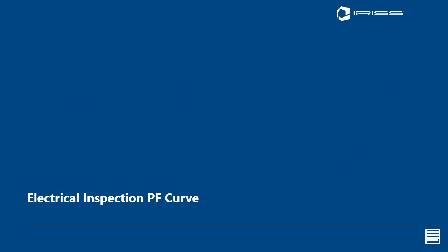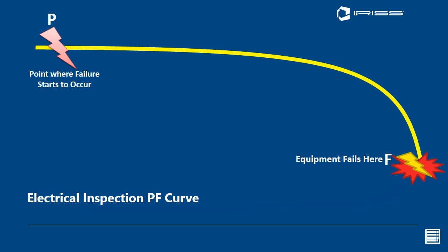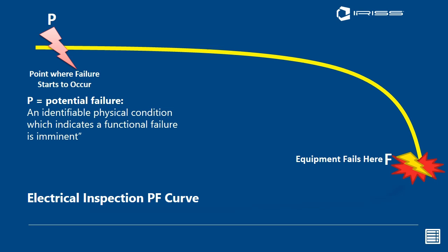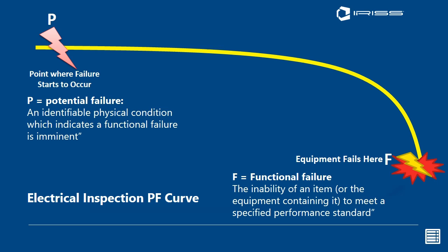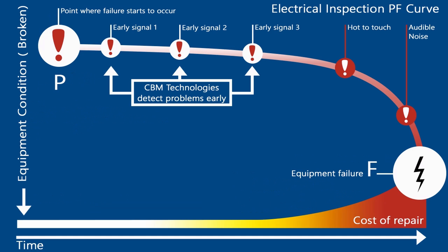When we look at an electrical inspection PF curve, we see two areas here. The P stands for area of potential failure, which is an identifiable physical condition which indicates a functional failure is imminent. And a functional failure is the inability of an item or the equipment containing it to meet a specified performance standard. So I suppose you could say, if we were looking at a 480 volt piece of switchgear, its functional failure would be the inability to provide electrical power. When we look at the PF curve, we can see it's really imperative to try and identify the failure as soon as possible after the failure occurs.